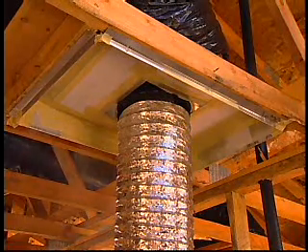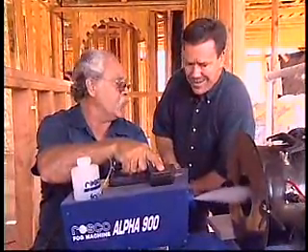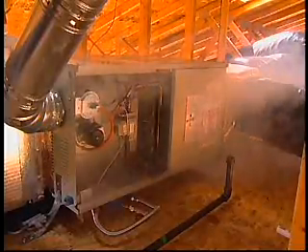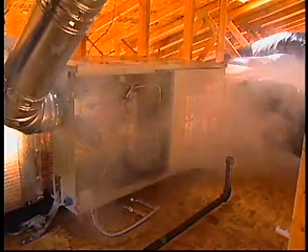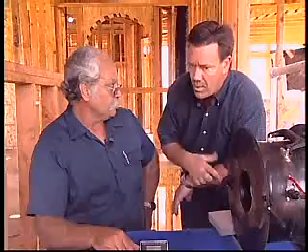I can see quite a bit of smoke coming through the return side, which is important because that return air duct is up in the attic — meaning it could be sucking in 140-degree attic air into the air handling unit, which really reduces efficiency and capacity. There's also quite a bit leaking out of the furnace unit itself, and there's not much the builder can do about that — the HVAC contractor needs to spend additional attention sealing up the equipment as it comes from the factory.